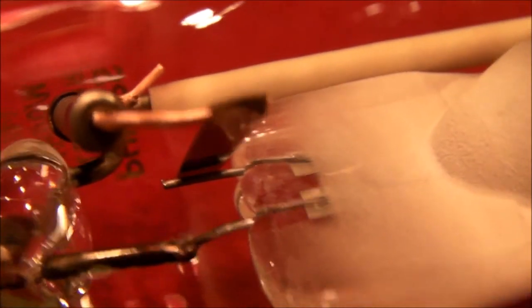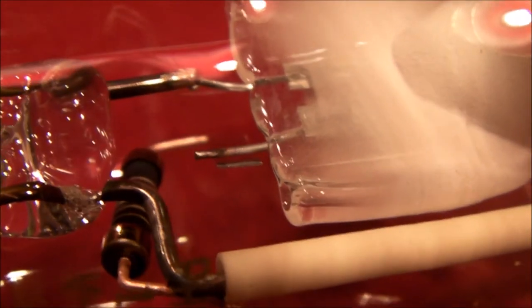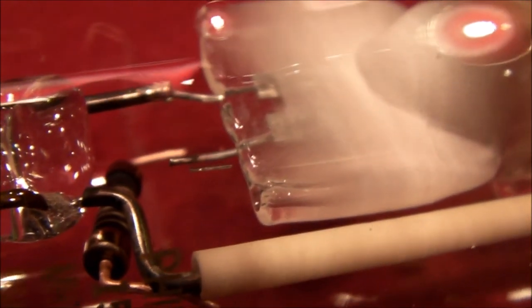Just thought I'd share this with you. You can see on that electrode there's a gap - no contact being made - so the light will not ignite and won't start.